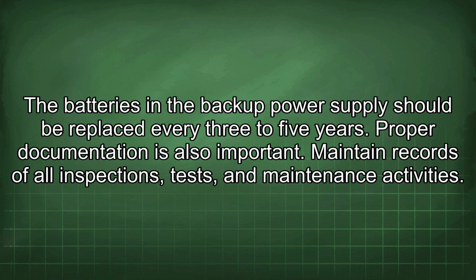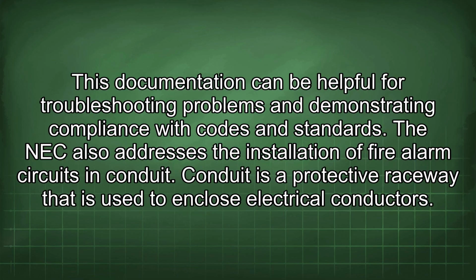Maintain records of all inspections, tests, and maintenance activities. This documentation can be helpful for troubleshooting problems and demonstrating compliance with codes and standards. The NEC also addresses the installation of fire alarm circuits in conduit.